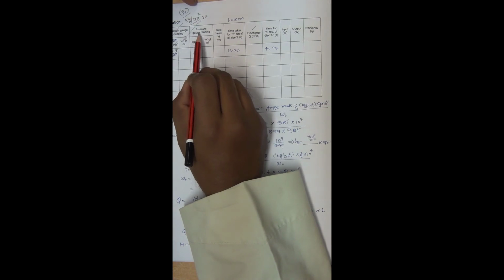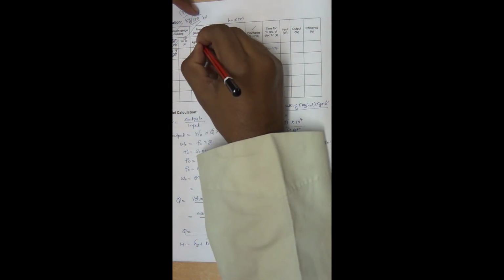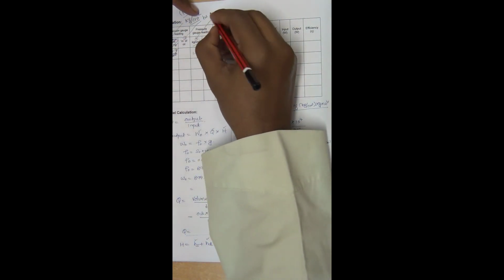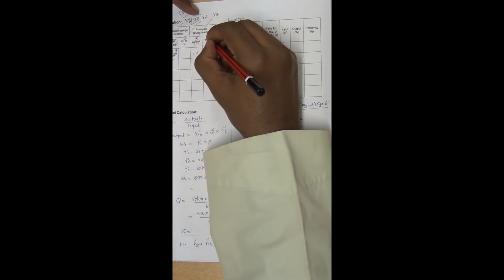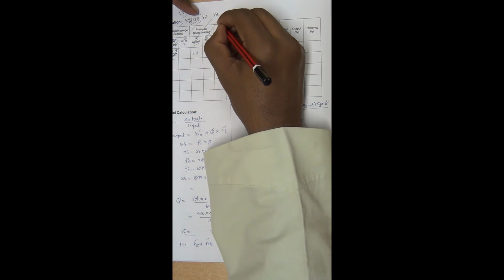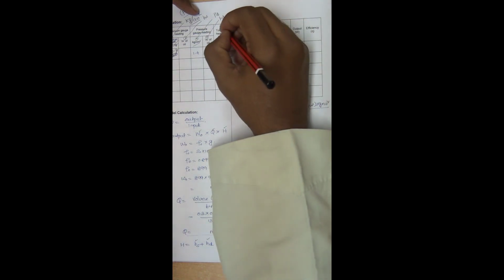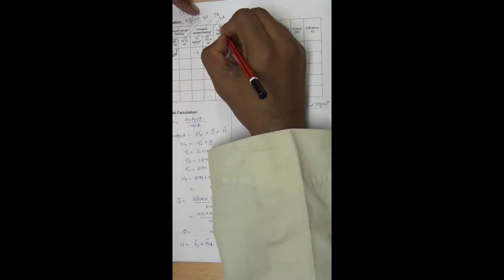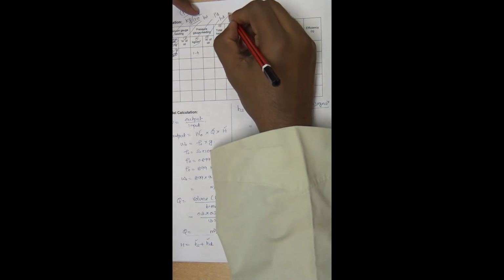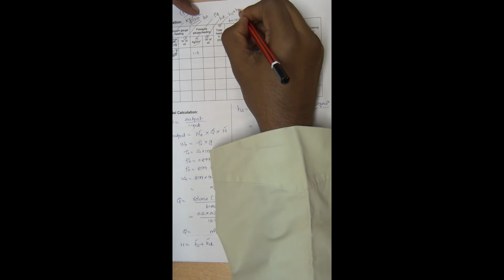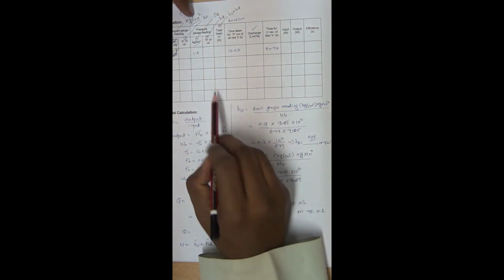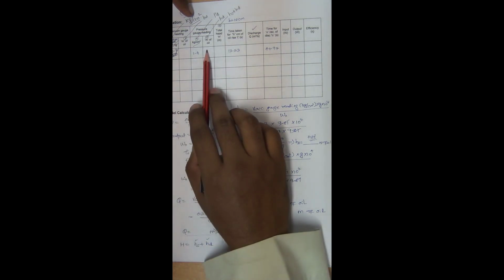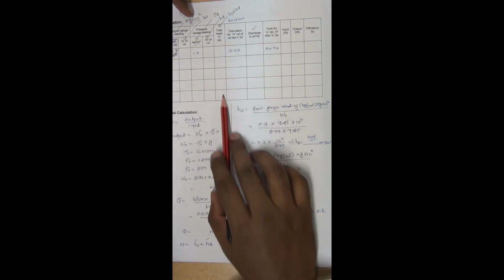Now the pressure gauge reading column, let us name it PD, delivery pressure, and this column HD, delivery head. Now what is total head? Total head capital H is nothing but HS plus HD. So we add this column and this column to get total head. We have calculated these columns and total head also.